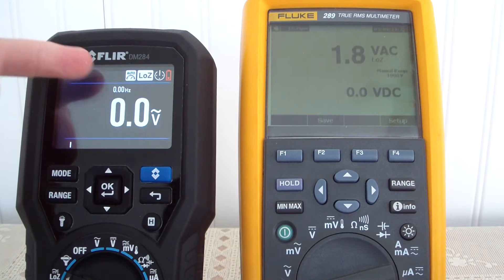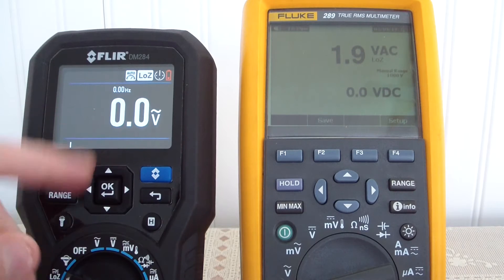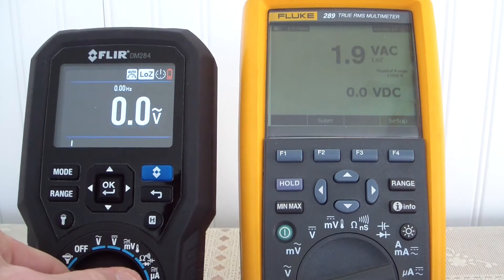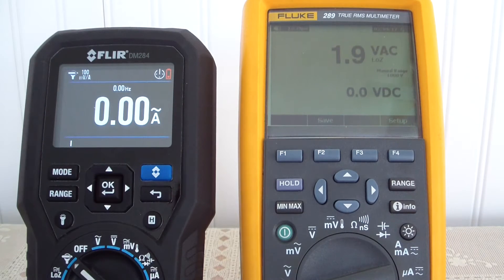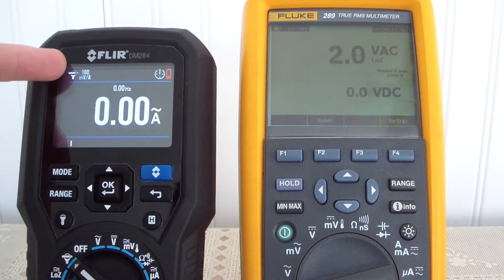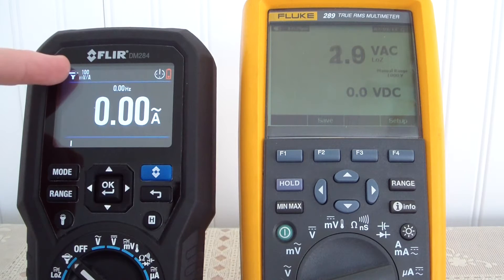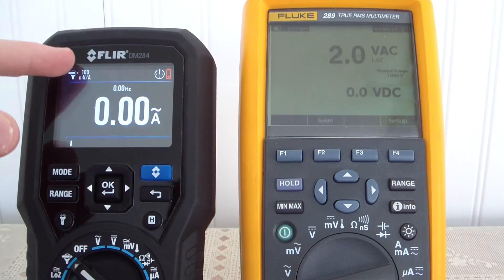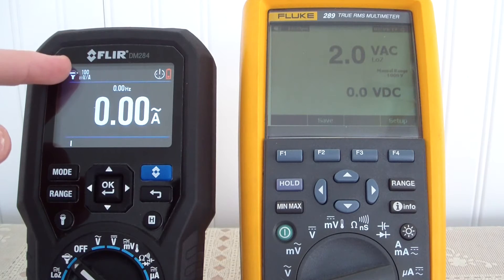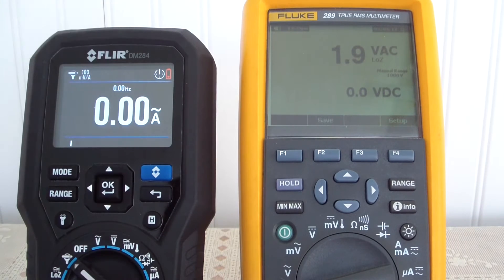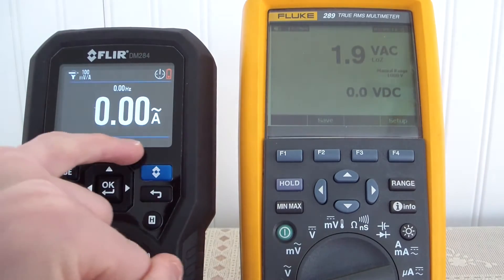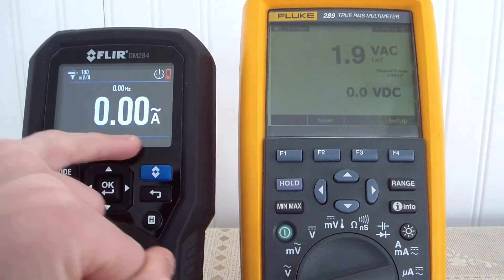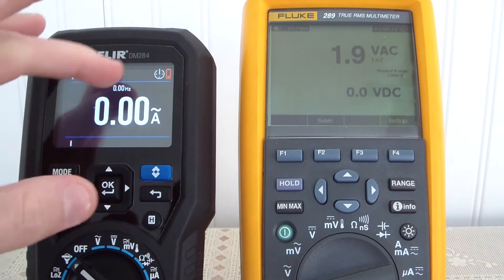The FLIR has a dedicated amp probe switch; the Fluke does not have that. So you are able to go between 1 millivolt/1 amp, 10 millivolts/10 amps, or 100 millivolts/100 amps. Down at the bottom there is an analog bar graph, and you have your Hertz on top and AC on the bottom.